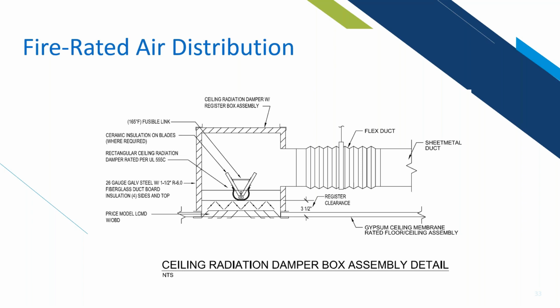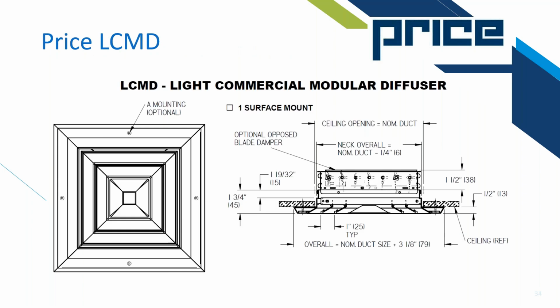What you need to do is actually apply a ceiling radiation damper boot, like you can see here, and then actually have your supply diffuser in the face of that, so that there's no wood exposed to the heat that could happen from a fire. So we have a really great option here where we can put a full price LCMD with an OBD, opposed blade damper, in the back of it, so you can get volume control, you can get a nice quality diffuser, and you can meet your UL expectations in that assembly.